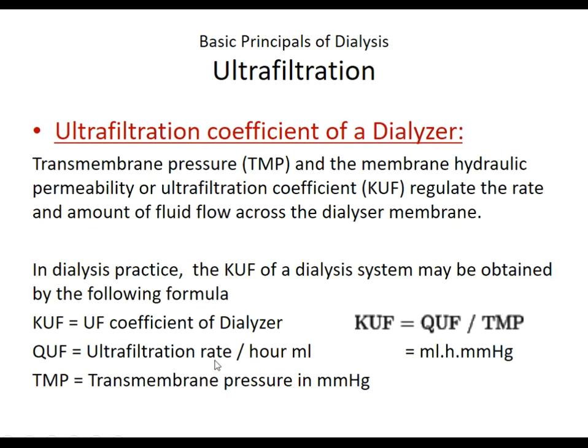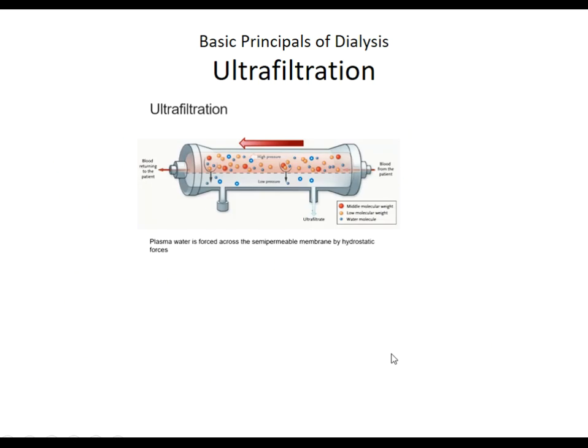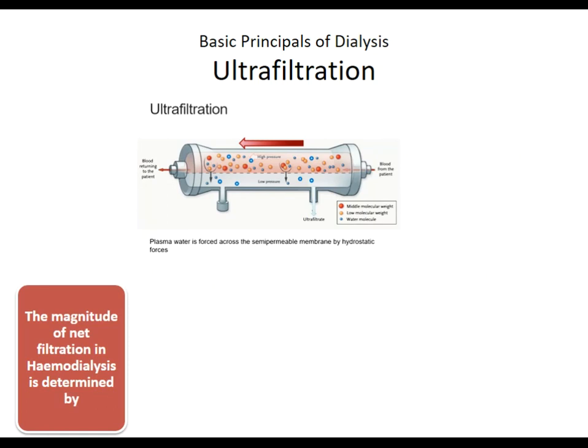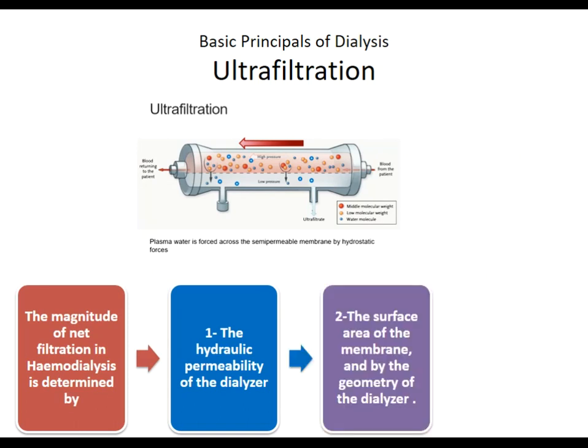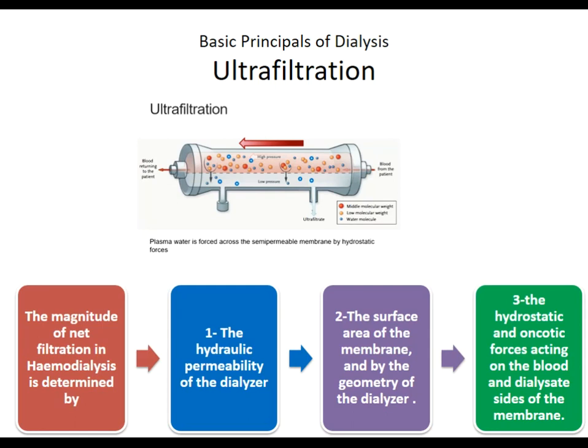The transmembrane pressure and the membrane hydraulic permeability — or ultrafiltration coefficient (KUF) — regulate the rate of fluid movement across the dialysis membrane. KUF is the ultrafiltration coefficient of a dialyzer, measured as ultrafiltration rate per transmembrane pressure in millimeters of mercury. The magnitude of filtration in hemodialysis is determined by the hydraulic permeability of the dialyzer, the surface area of the membrane, and the geometry of the dialyzer — the narrower fiber has more ultrafiltration capacity. Hydrostatic and oncotic forces acting on the blood limit ultrafiltration. Increased hydraulic permeability and increased membrane surface area increase ultrafiltration, while increased hematocrit and protein content of the blood limit ultrafiltration.